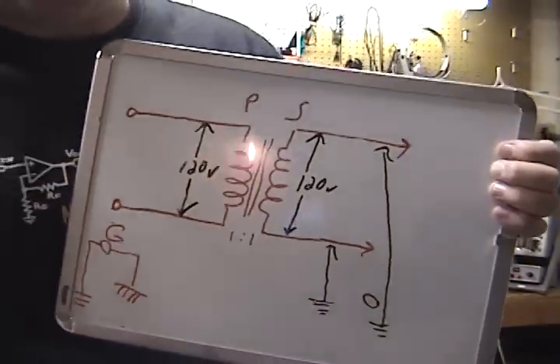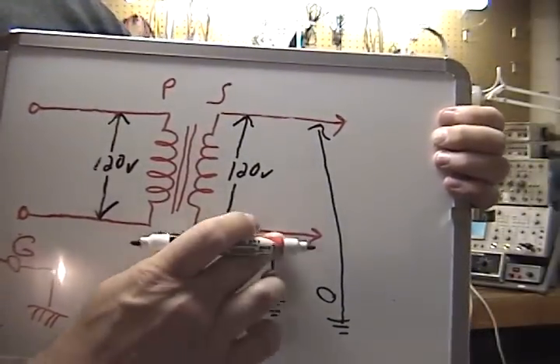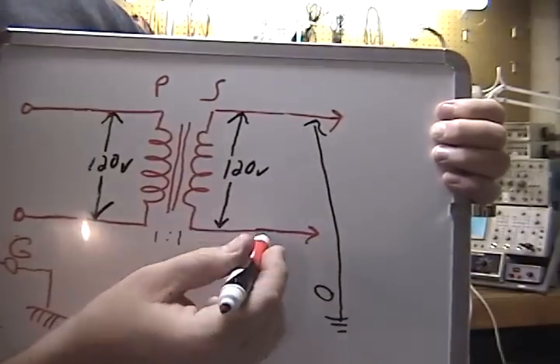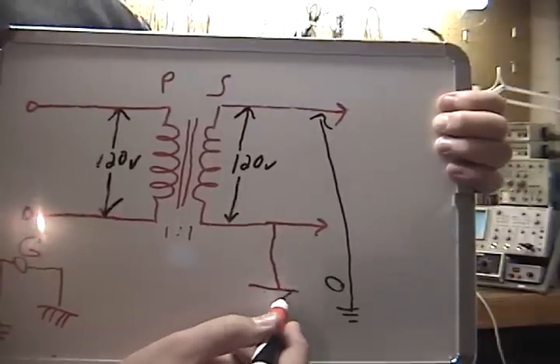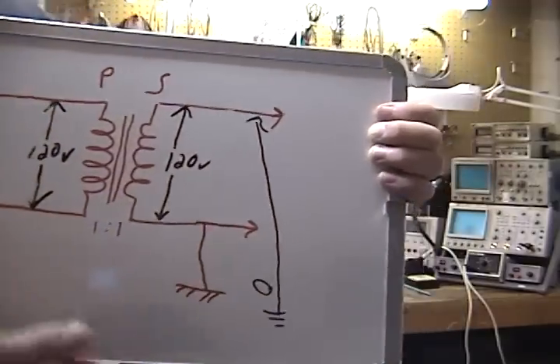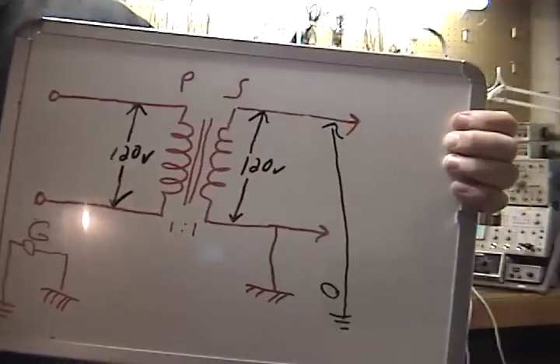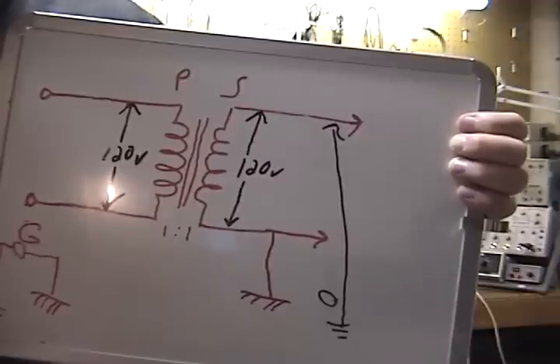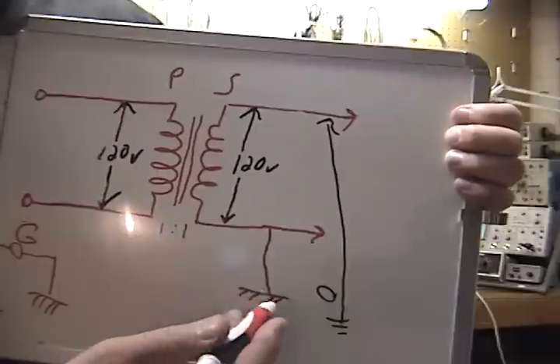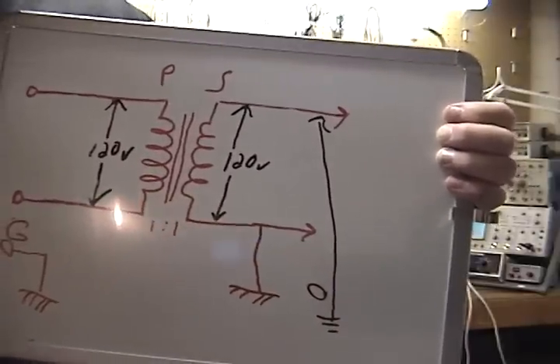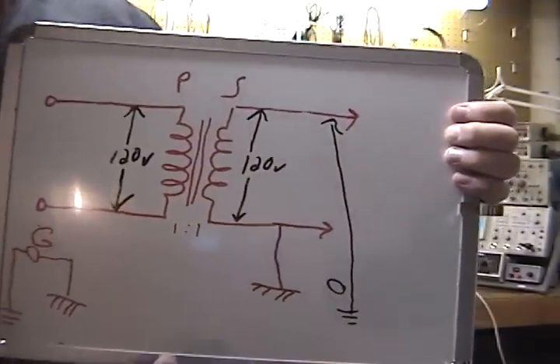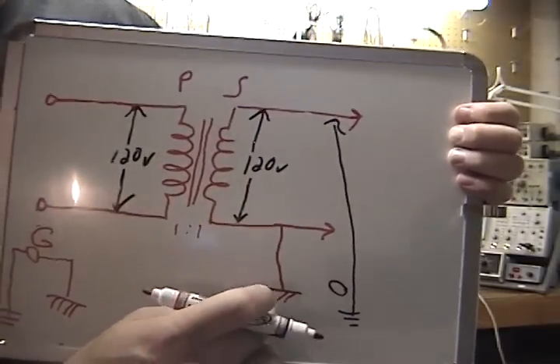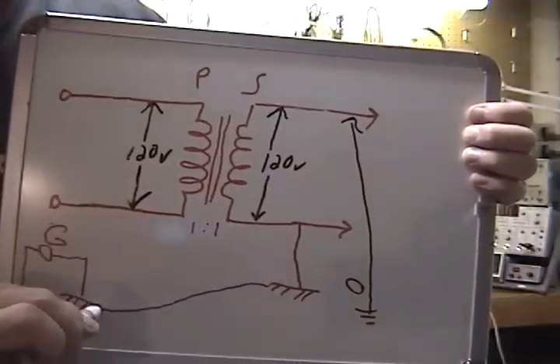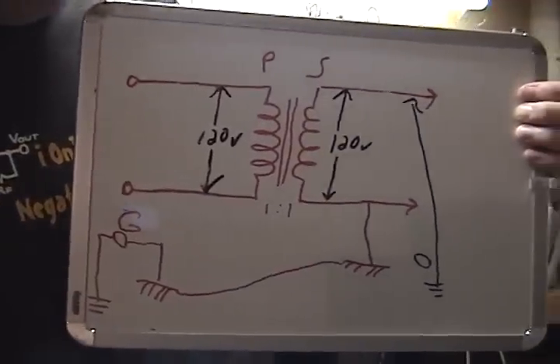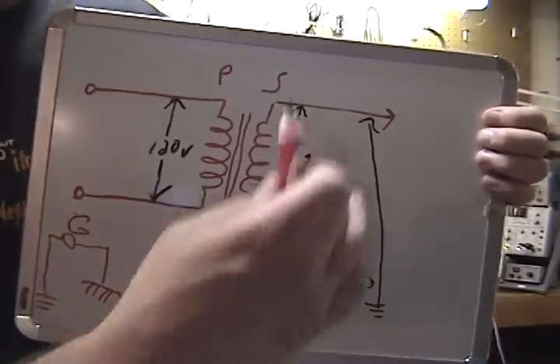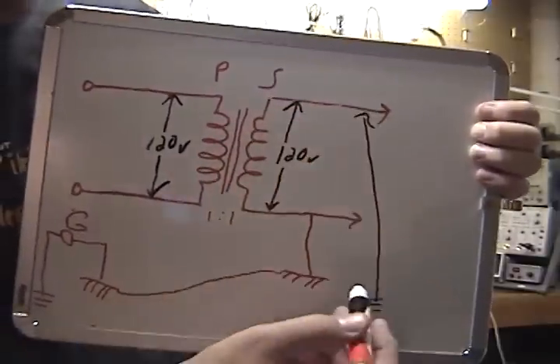If you have a public version, like a Tripp Lite isolation transformer, what they do is they actually have a strap - we'll go ahead and put it in. They strap this secondary coil windings to the chassis. Now they do that for common mode noise rejection, so the signals are cleaner for the equipment hooked up to this thing. It's also an NEC requirement, so they kind of have to do it, because this produces a second neutral for your secondary system, which is great for that purpose, but it's really poor for you as a technician. Now if I measured, this point becomes the same as this chassis point over here, and that goes to ground. So now you have a ground referenced, high voltage ground referenced environment on your secondary. So if I measure it over here now, this secondary would have 120 volts on it.